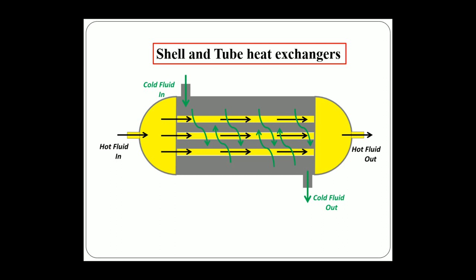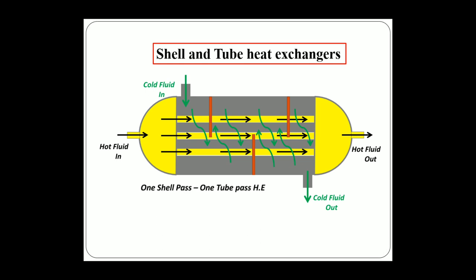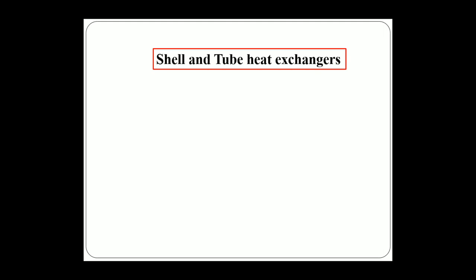Shell and tube heat exchangers are named based on the term 'pass.' A pass refers to how many times the fluid moves from one side to the other — left to right or right to left. Here, the hot tube fluid moves from left to right in a single pass, and the shell fluid also moves in a single pass. Baffles are also present to create turbulence within the shell fluid, increasing heat transfer. This configuration is known as one shell pass, one tube pass.